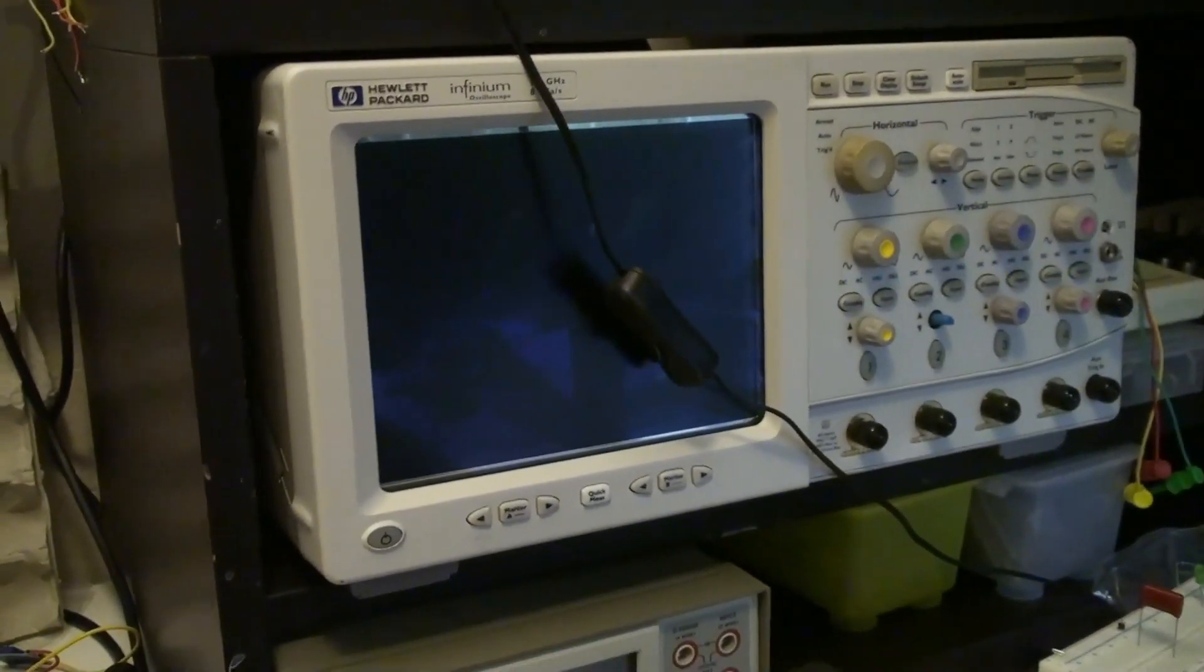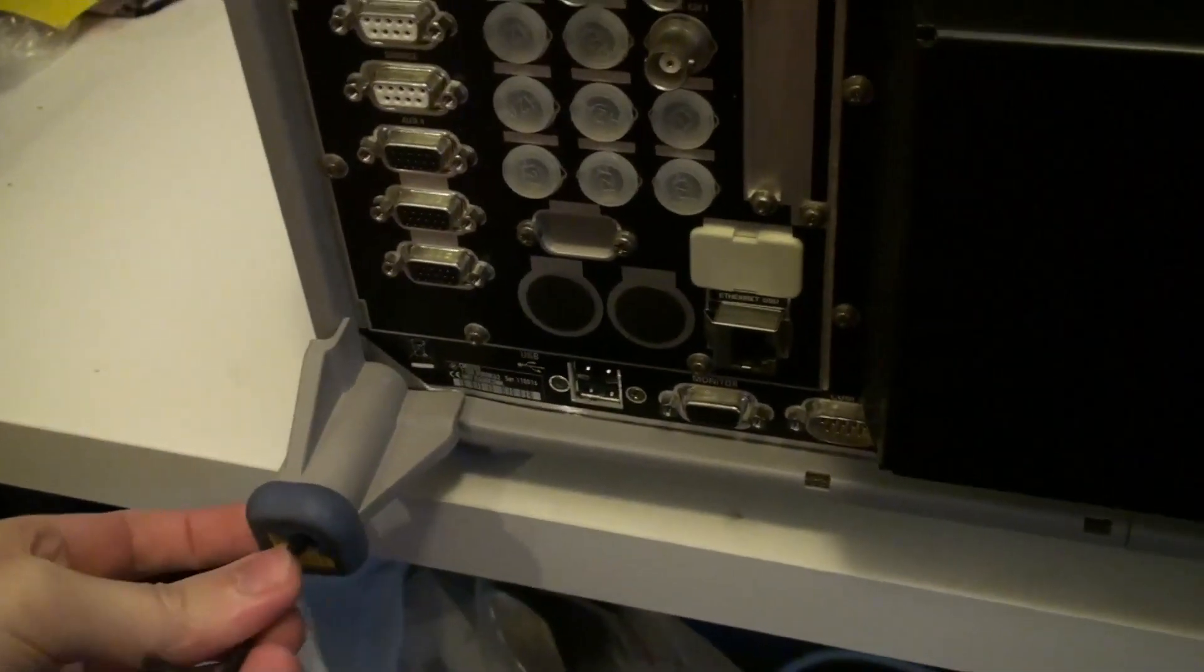So unlike the HP up here where the handle is actually part of the inner case. So there you do need to take off the handle. Because it actually holds on the outer case. Here you don't.